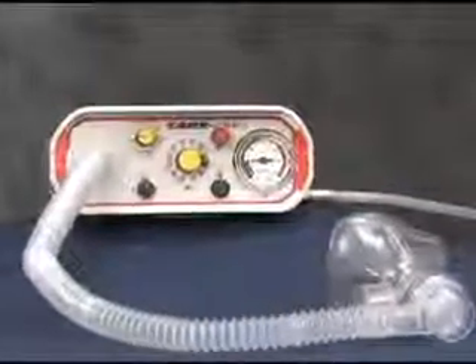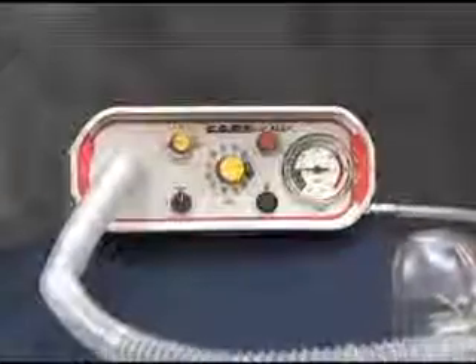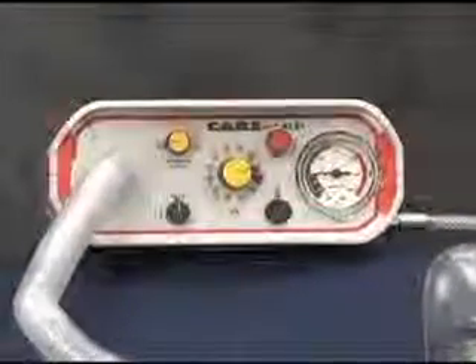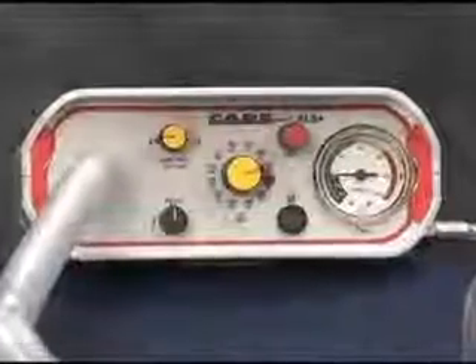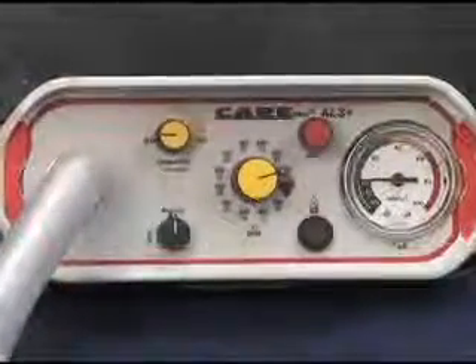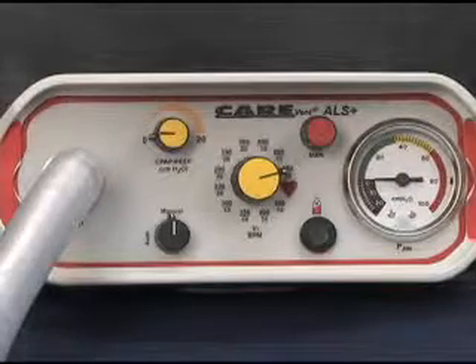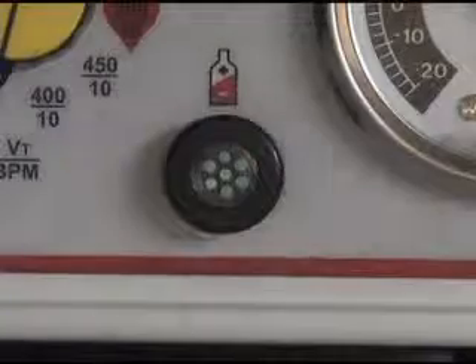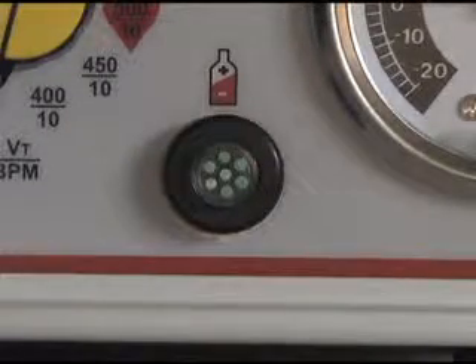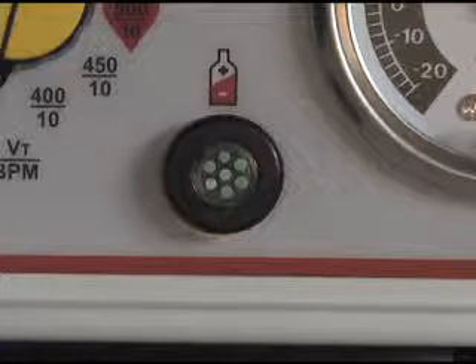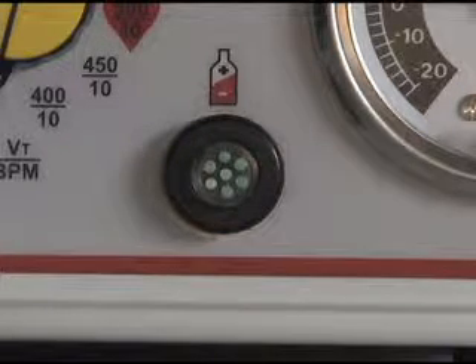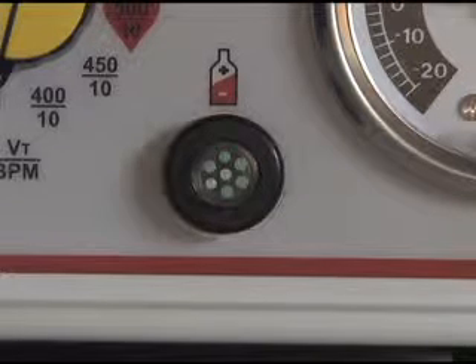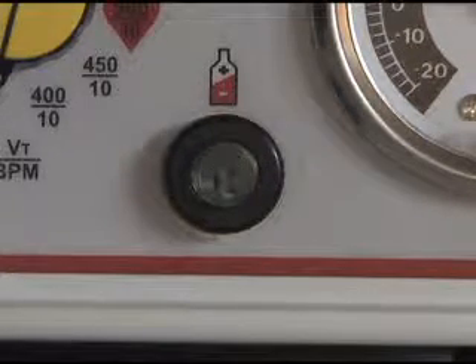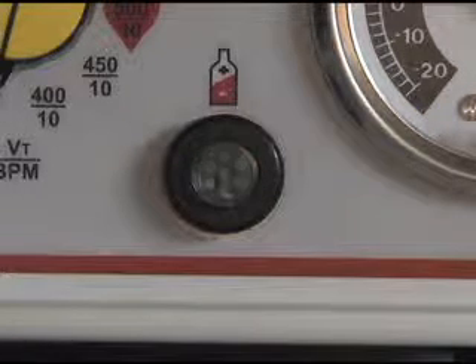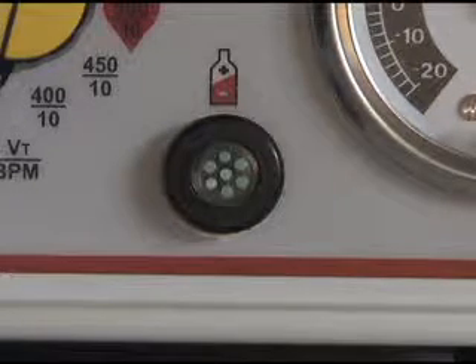The CAREvent ALS Plus and ALS Plus CPAP control module style automatic transport ventilators provide automatic and manual ventilation for resuscitation and transport, and have the added feature of demand breathing for the patient suffering from respiratory distress. The green visual gas supply indicator and short audible tone will confirm that the gas supply is turned on. Should the gas supply pressure drop below 40.6 pounds per square inch, the visual indicator will flash green to black, and a pulsed audible alarm will activate, warning the rescuer that the gas supply pressure is running low.